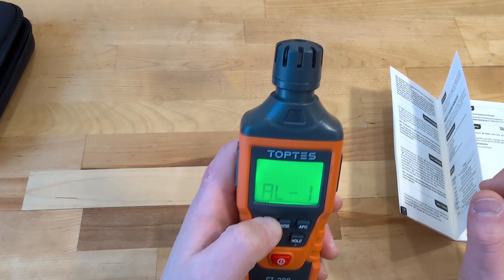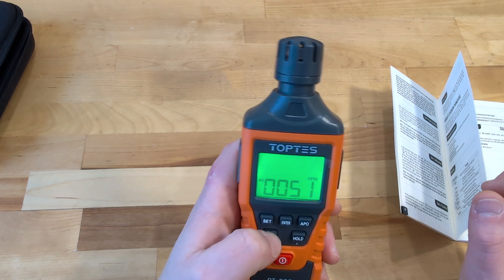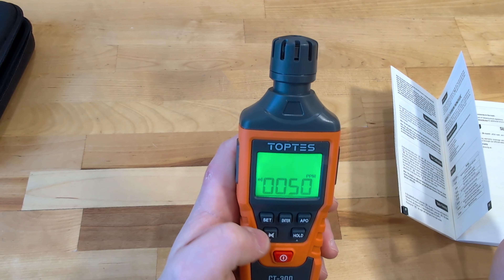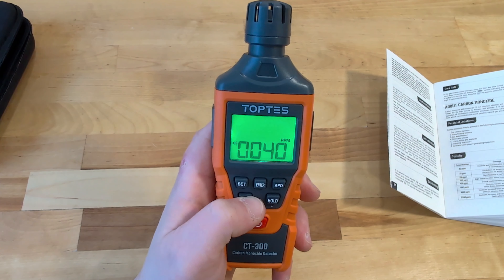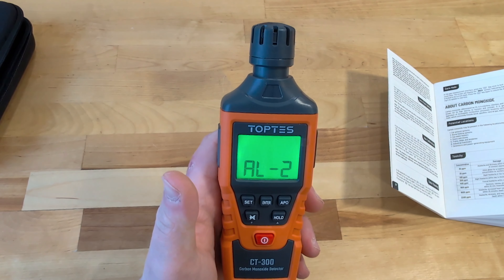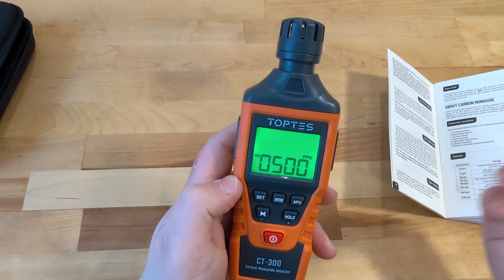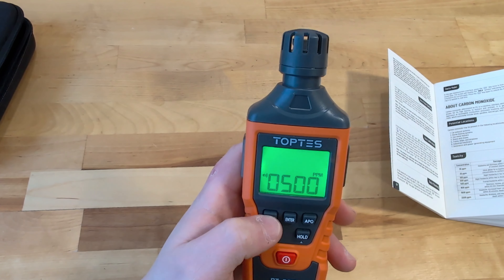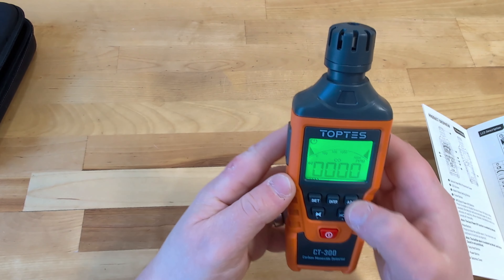So if I wanted to, I can set this and move that up or down with these two buttons to a safety level that I want. Anything over 35 is going to be a concern, so let me move that down. We'll get an audible alert as well as a visual alert if that happens. Our second level of safety at 500 sounds about right, because we wouldn't want to stay in the room if that was the case. I'll go ahead and save those.